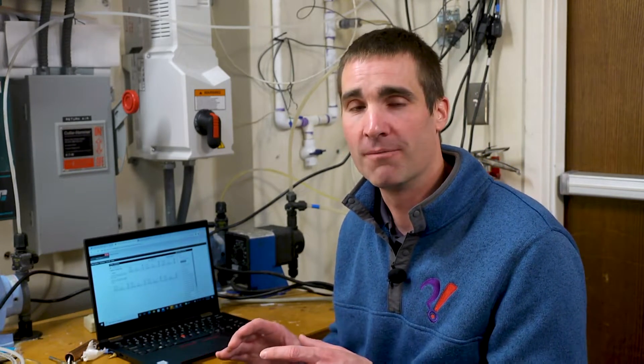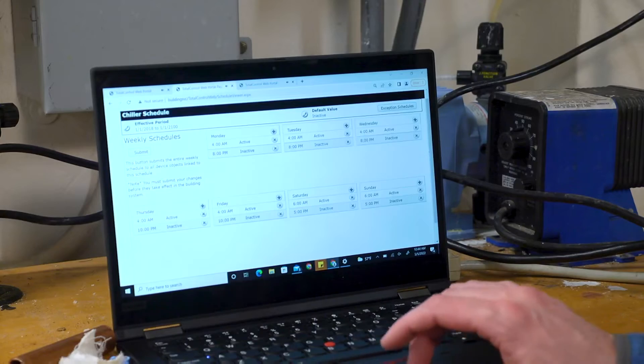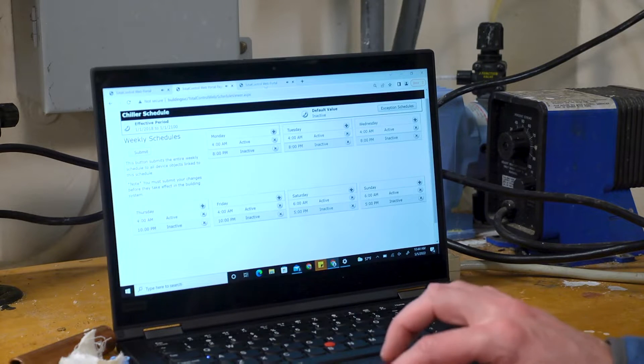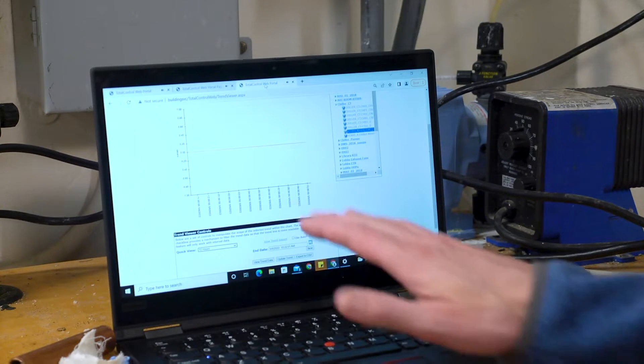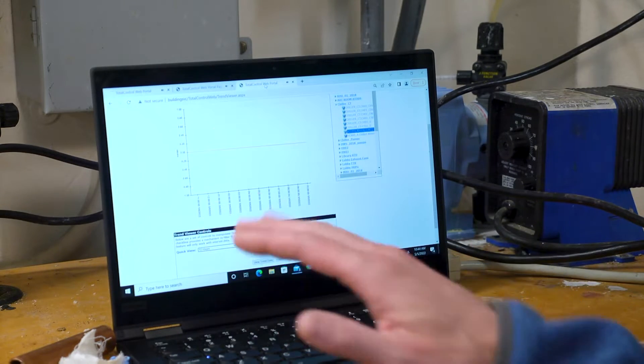In addition to that, not only reviewing the schedules, it's good to use building automation systems to get the feedback to know that the systems are actually disabling when they're supposed to. So I know from this operating schedule that this chilled water system shouldn't have been running this past night. I could go back and look on the automation system and look at last night's trends to make sure that indeed the chiller was disabled when I thought it was supposed to be.